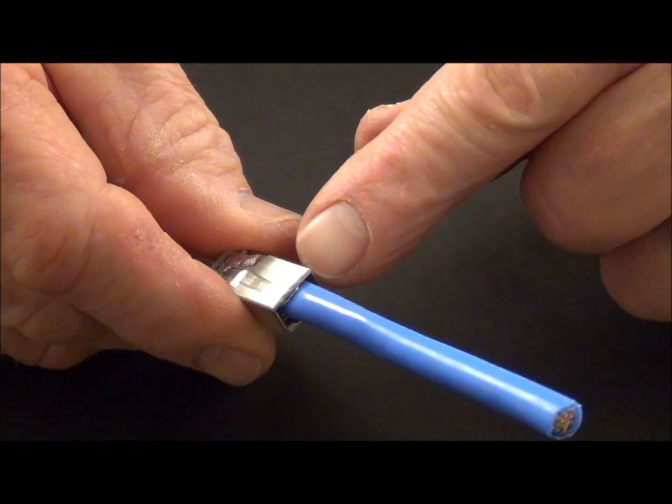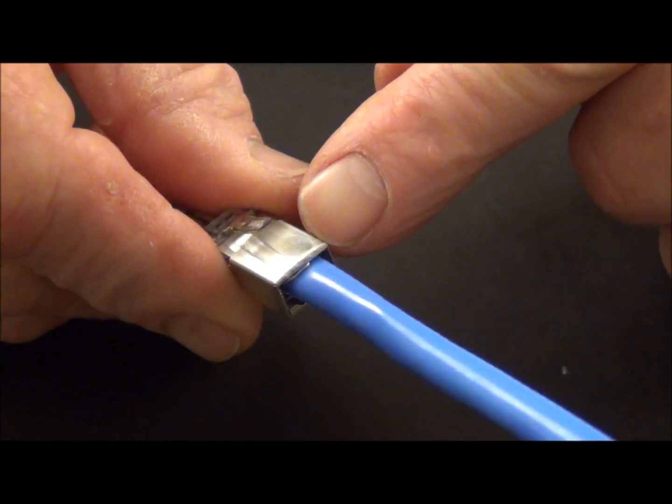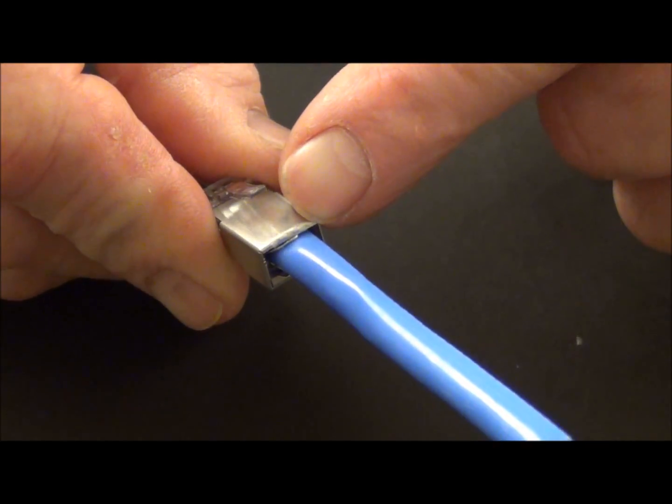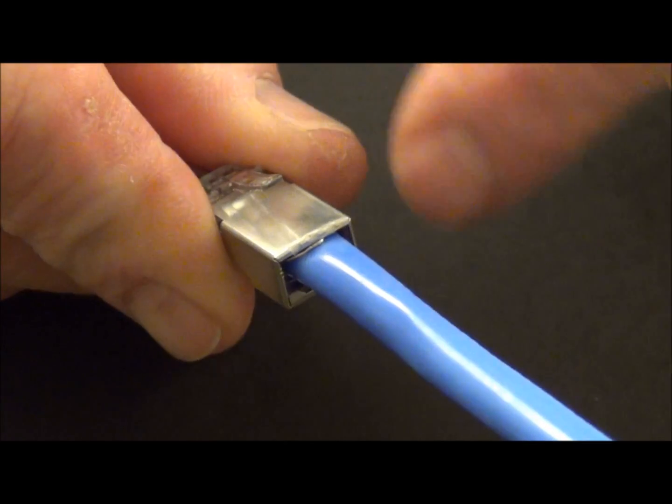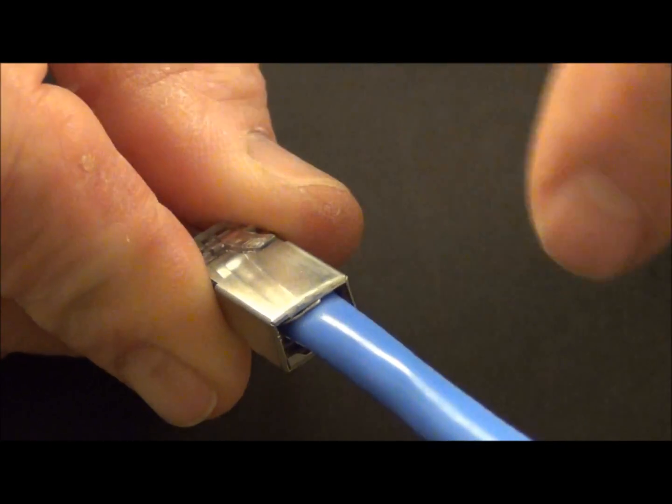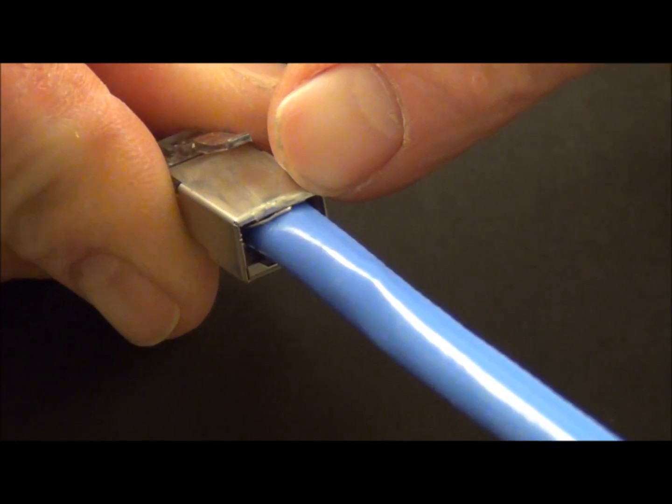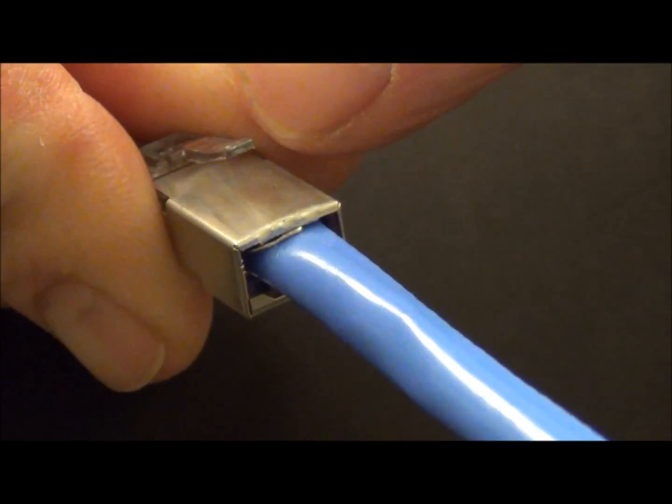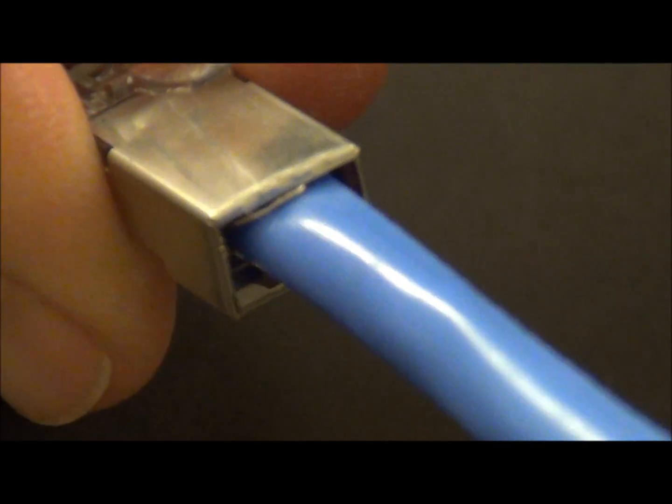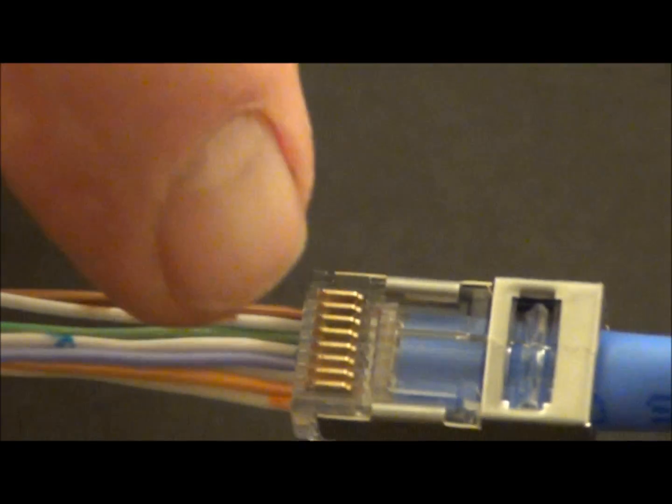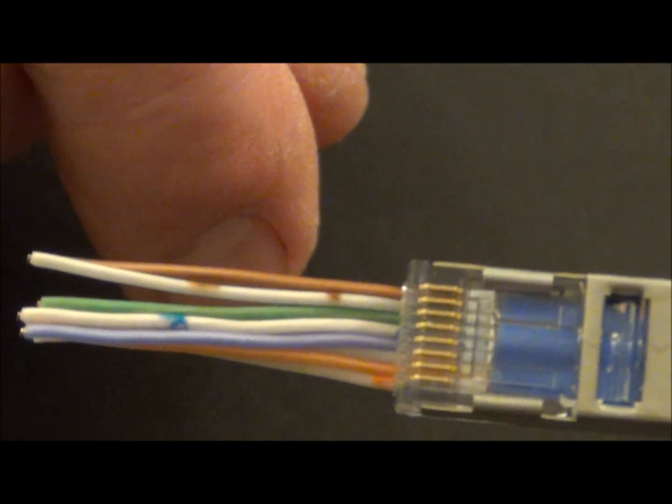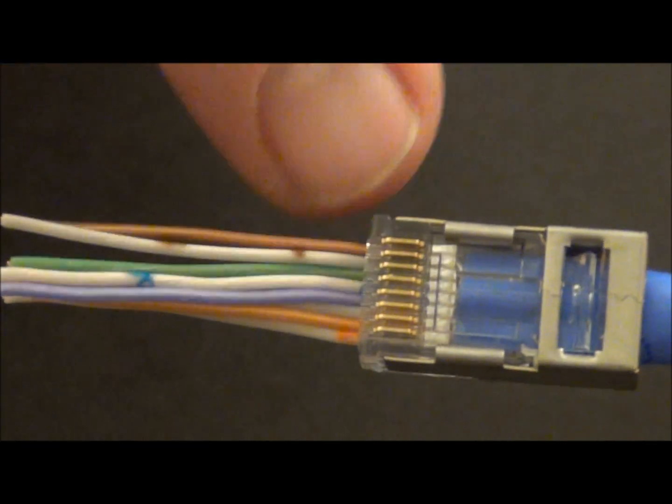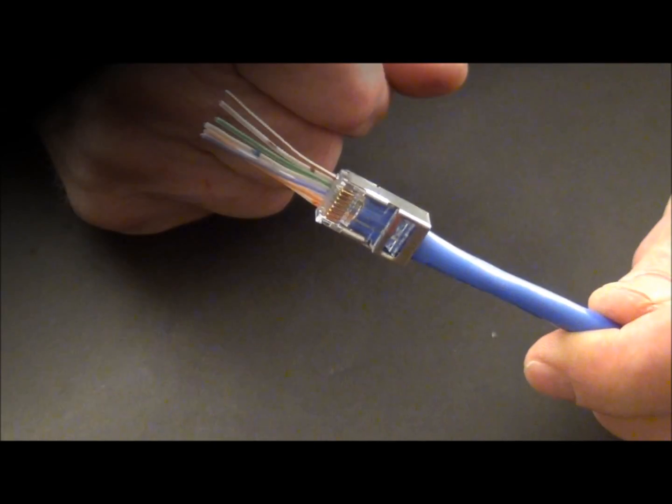Okay, here's the back end. You can slightly see my ground wire. I looped it and foiled it around. But you can see it right there at the back end. It's sitting really nice on those springs. It's going to be a good ground. And then am I going to meet Cat 6? Yes, I will. Because my twists, see the end of the jacket, are right there where they belong at the back of the contacts. So here we go, Cat 6, internal ground, ready to be terminated.